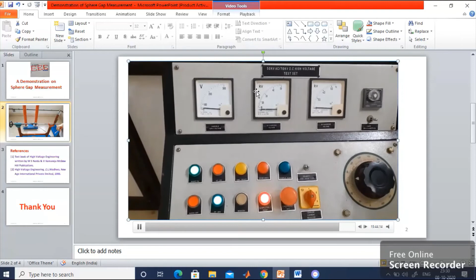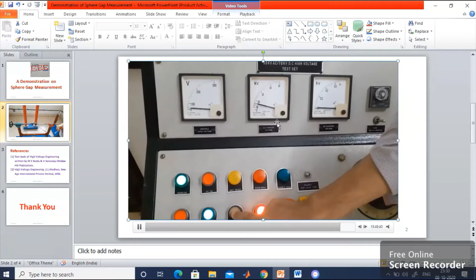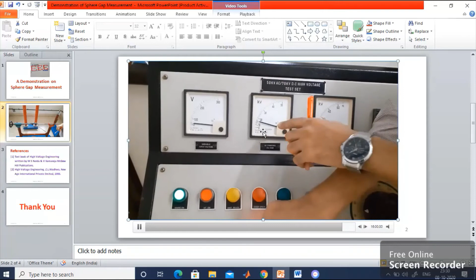Now, how to get the value of breakdown voltage? There is no worry, we have memory. By using the memory, you can find out the value. You can check, it is approximately 17 kV. The breakdown voltage, when you maintain the distance between two spheres equal to 10 mm, is 17 kilovolt.